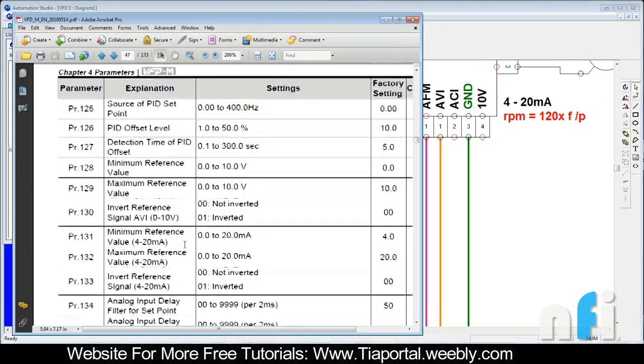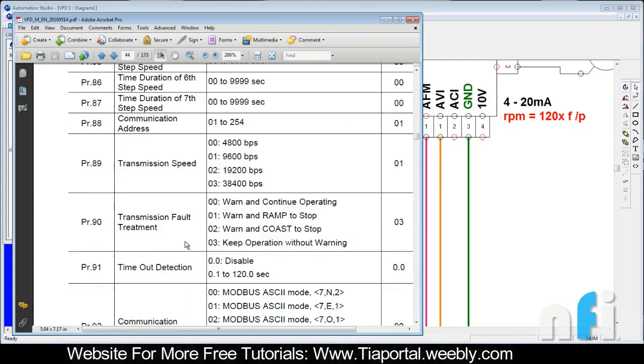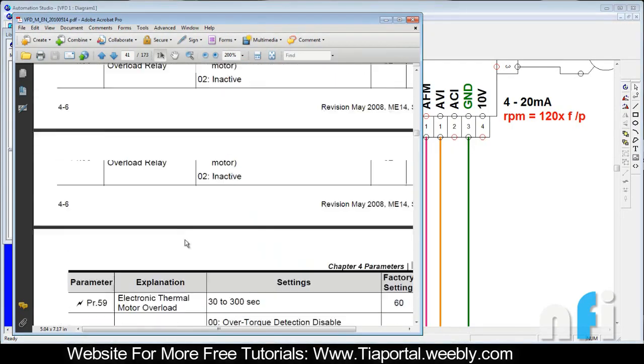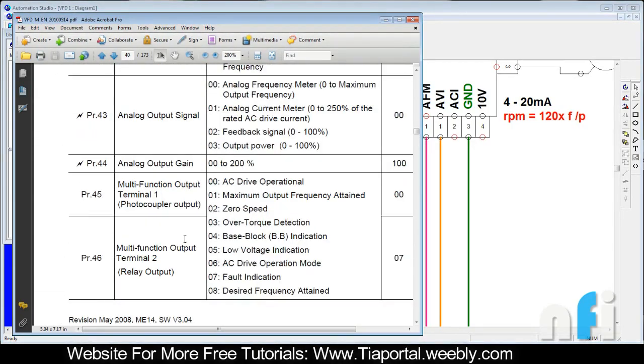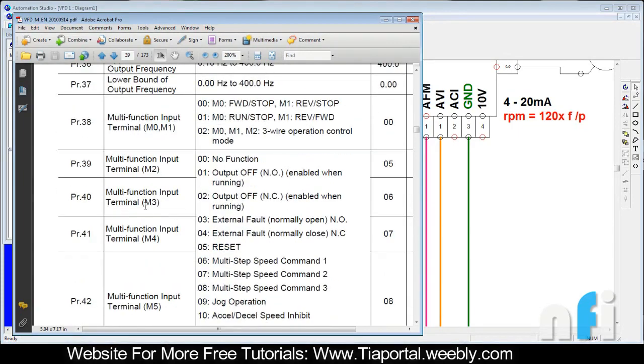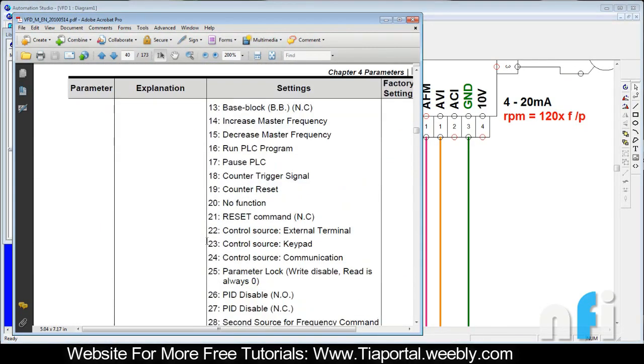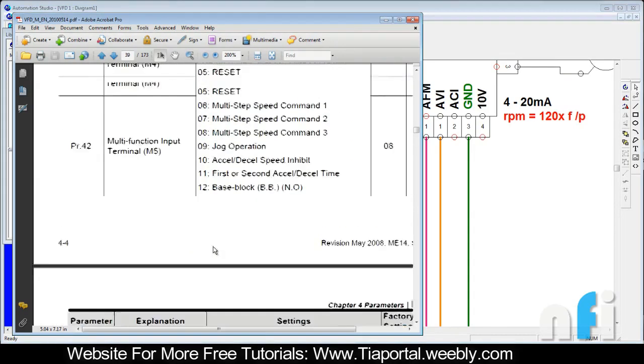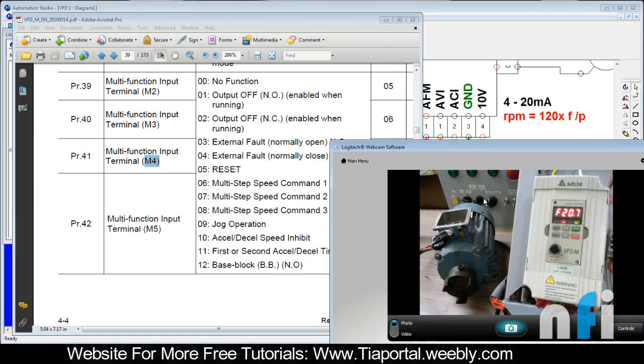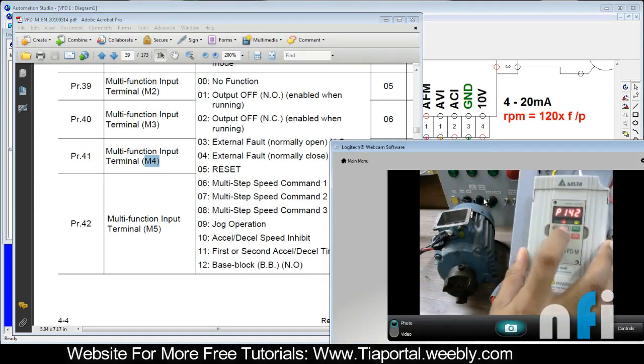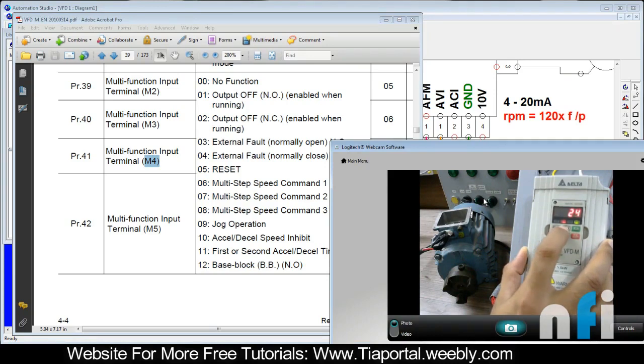So M4 has to be assigned this function. I'll go back to the parameter which works for M4, which is parameter 41. For that I will select second source of frequency, 28. So we have 28 in parameter 41. I went to 28.